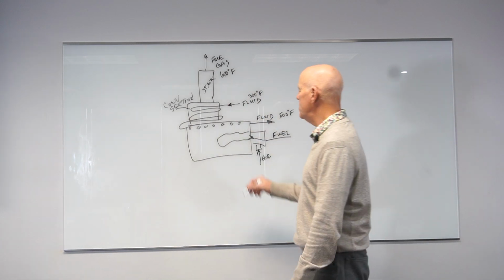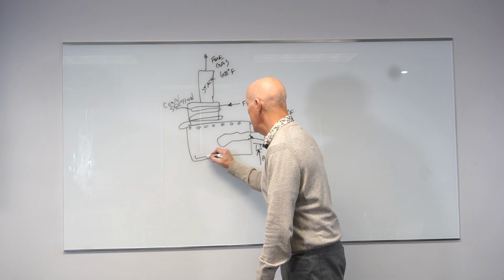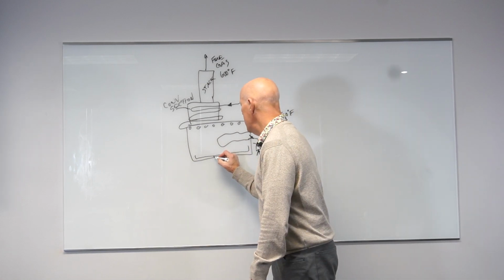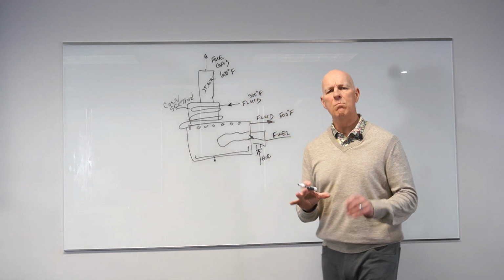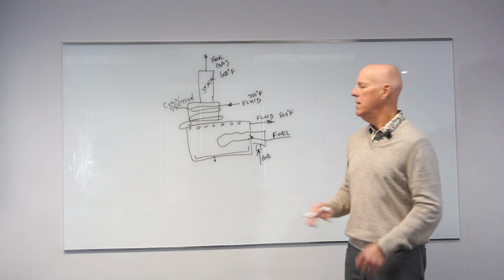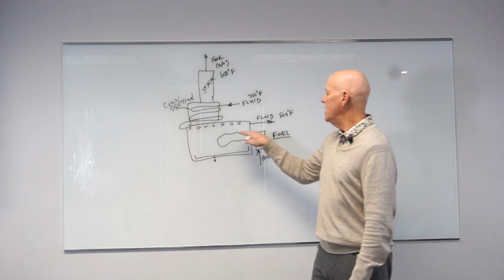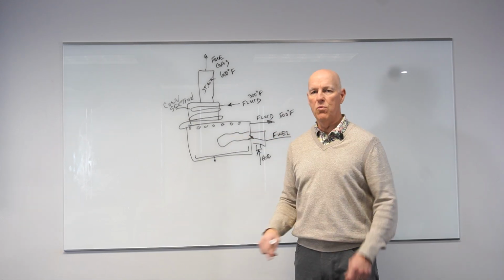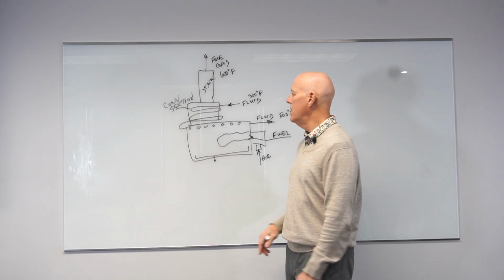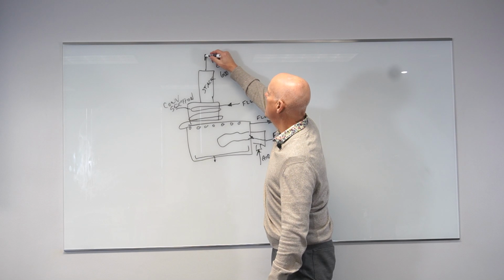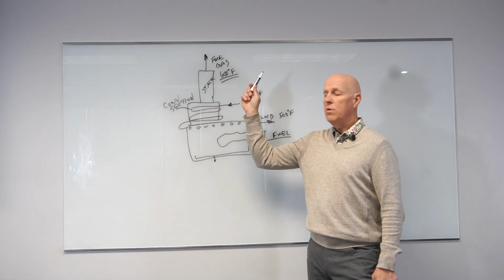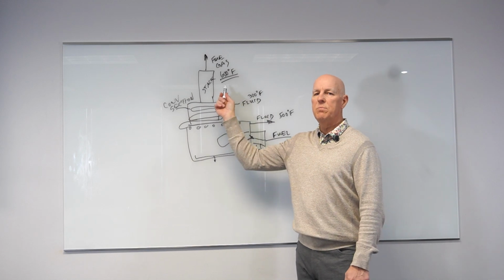Another place that I lose energy is inside this heater. Of course, we have what's called refractory, which is like insulation, and so I lose a little bit through that. Not much, almost inconsequential, like maybe 1% of the duty, 1% of the energy that's used in this fuel firing comes through the wall, because I'm going to insulate that, kind of like a Yeti in reverse. So really what it gets down to is, how do we get this temperature lower? Because we know if we want to increase the efficiency, this needs to be lower.